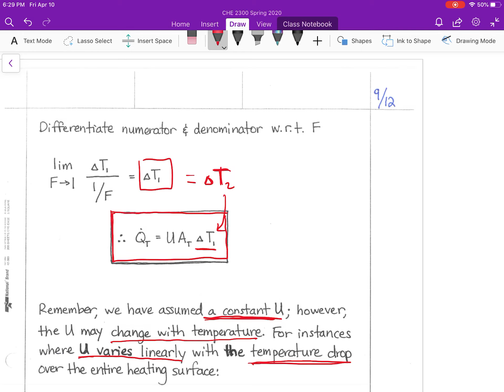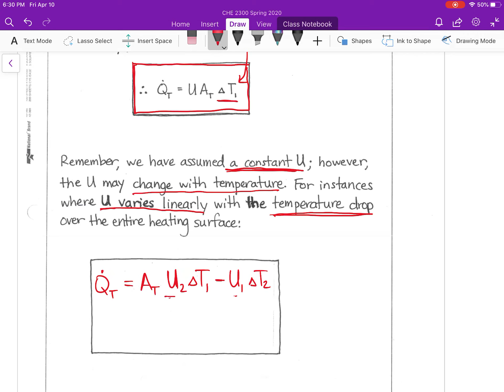So the total amount of heat transfer, total heat flow, is equal to my total area of heat transfer. And now this is multiplied by an overall heat transfer coefficient on one side of the heat exchanger multiplied by delta T1, minus my heat transfer coefficient on the other side of the heat exchanger multiplied by delta T2. And then all of that is divided by the natural log of the ratio of those two terms.